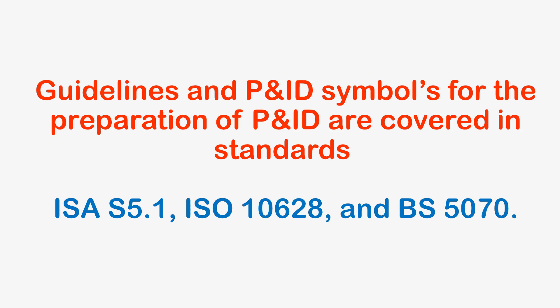Now let's get into P&ID symbols. There are lots of P&ID symbols used to represent equipment, piping, instruments, valves, and control valves. Piping design engineers must be well conversant with P&ID symbols to be able to read the P&ID. The guidelines and symbols used for preparation of P&IDs are taken from standards such as ISA S5.1, ISO 10628, and BS5070.